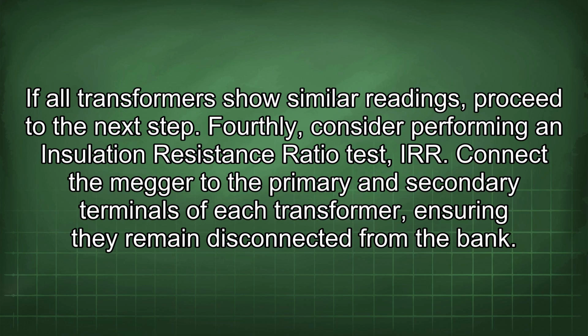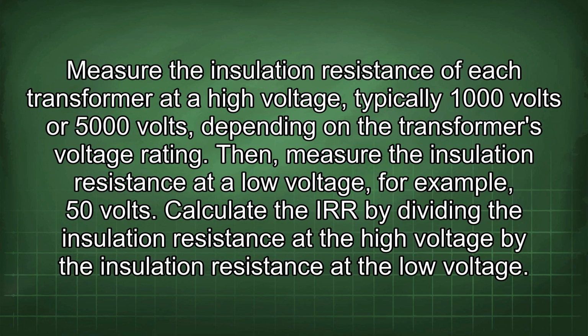Fourthly, consider performing an insulation resistance ratio test. Connect the megger to the primary and secondary terminals of each transformer, ensuring they remain disconnected from the bank. Measure the insulation resistance of each transformer at a high voltage, typically 1000 volts or 5000 volts, depending on the transformer's voltage rating. Then, measure the insulation resistance at a low voltage, for example 50 volts. Calculate the IRR by dividing the insulation resistance at the high voltage by the insulation resistance at the low voltage.